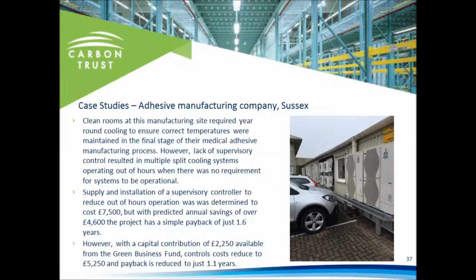And for air conditioning controls, this adhesive manufacturing company in Sussex, down south, had to maintain the internal temperature for its rooms, essentially clean rooms that were essential, with critical temperatures for part of its manufacturing process. Multiple split systems cooling multiple rooms were all on independent control, so many were running out of hours, many were overcooling. So the installation of a supervisory controller resulted in annual savings of over £4,600 per year, with a projected payback of 1.6 years. With capital contribution from the Green Business Fund, this payback was reduced to 1.1 years, and that's just with effective control of their air conditioning systems.